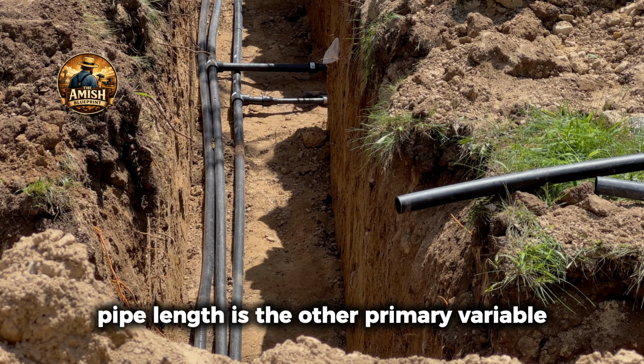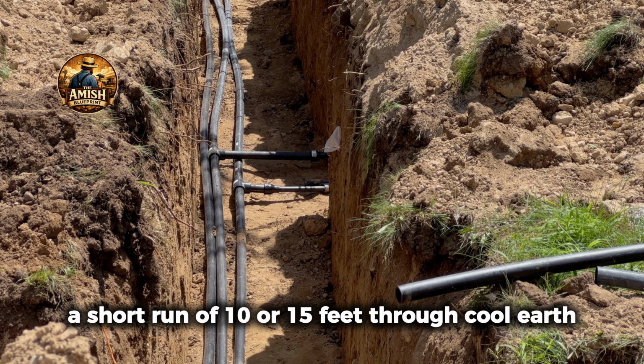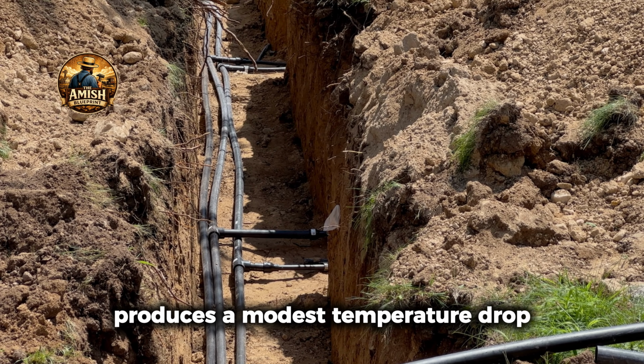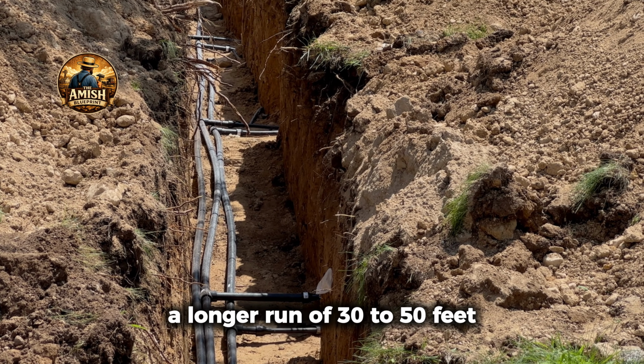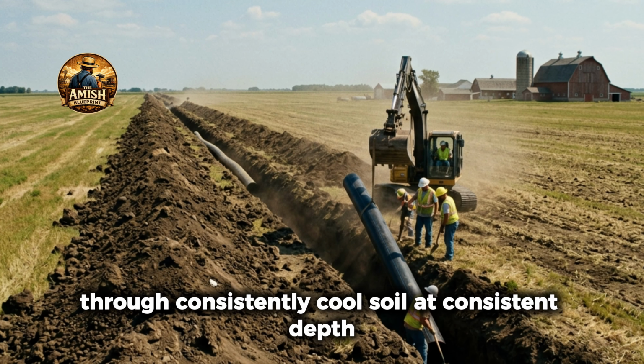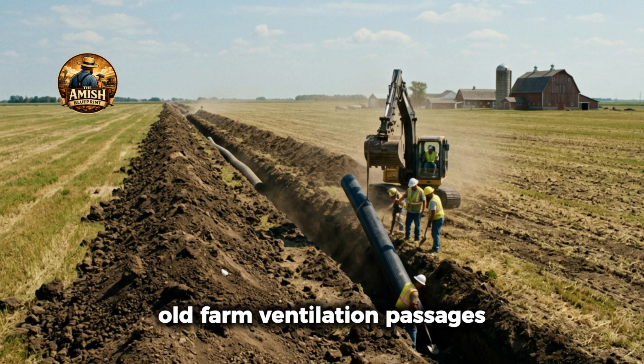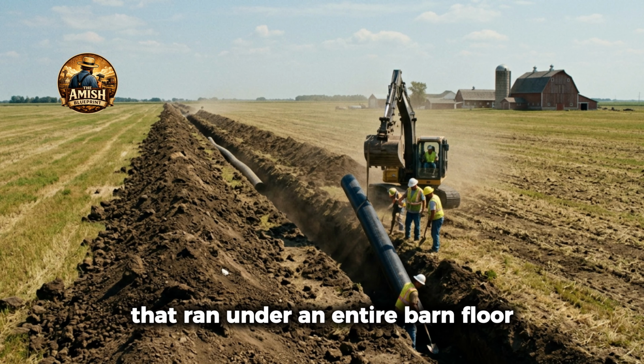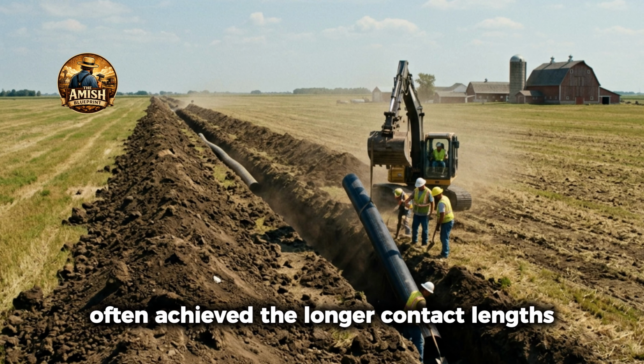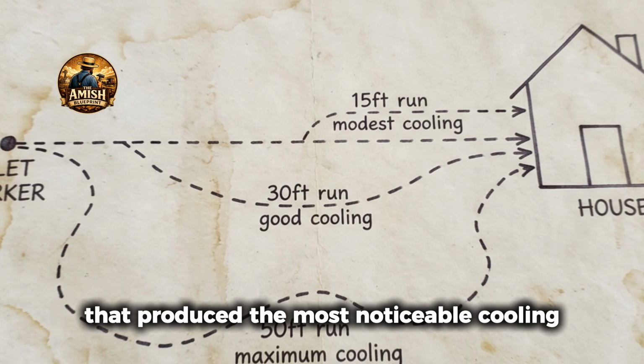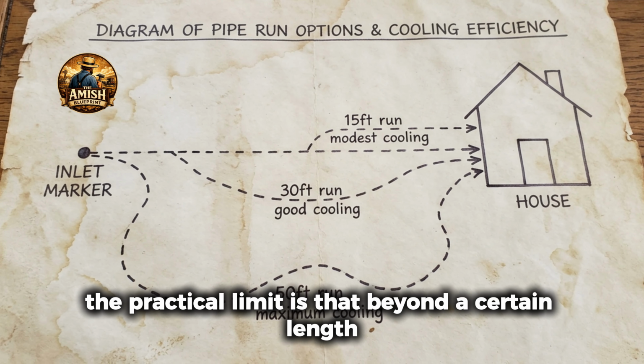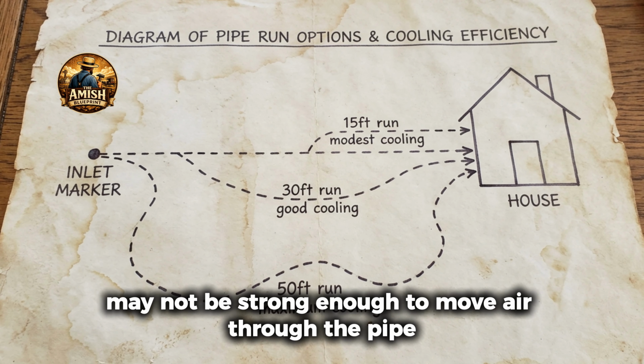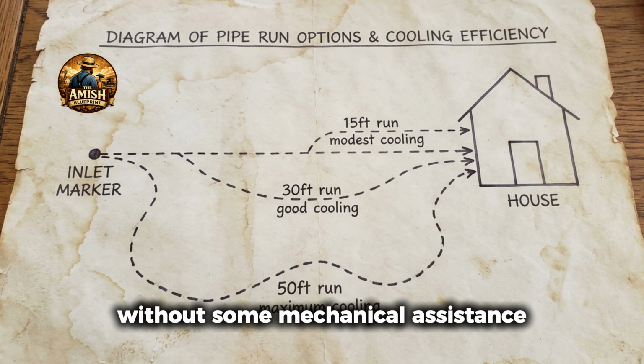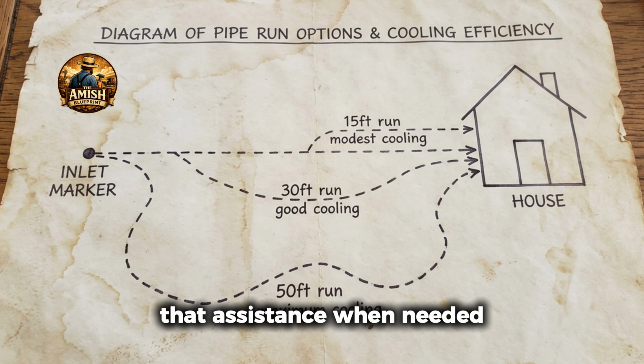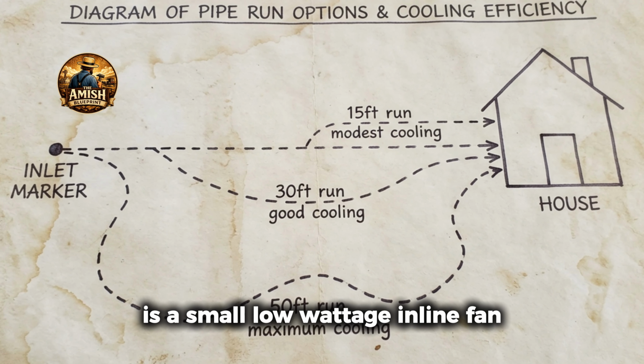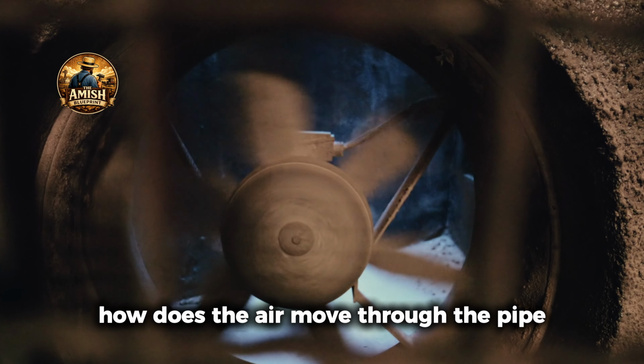Pipe length is the other primary variable. A short run of 10 or 15 feet through cool earth produces a modest temperature drop. A longer run of 30 to 50 feet through consistently cool soil at consistent depth produces a much larger one. Old farm ventilation passages that ran under an entire barn floor or along a root cellar wall often achieved the longer contact lengths that produced the most noticeable cooling. The practical limit is that beyond a certain length, natural convection may not be strong enough to move air through the pipe without some mechanical assistance. That assistance, when needed, is a small, low-wattage inline fan, not a compressor. How does the air move through the pipe?